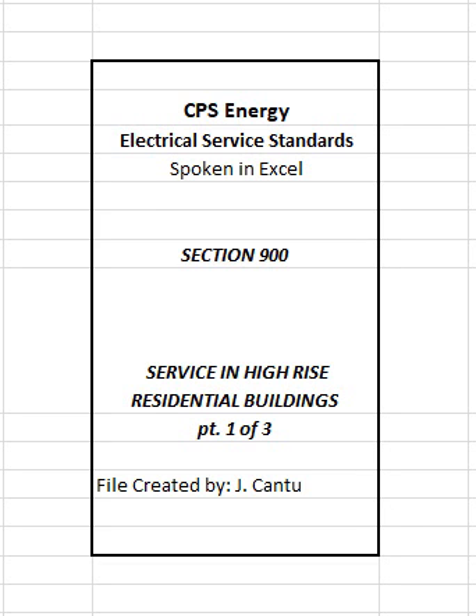902 Customer-owned service equipment. Customer shall furnish, install, and maintain service equipment at a readily accessible location approved by CPS Energy outside or inside of building. A. Provisions for tenant loads. Customer-owned service equipment shall be designed and used to supply feeder risers to metering equipment located in CPS Energy-approved meter rooms located on every third floor within building. Customer shall be responsible for balancing all tenant loads on the 208Y/120 volt, 4-wire Y service supplied by CPS Energy.